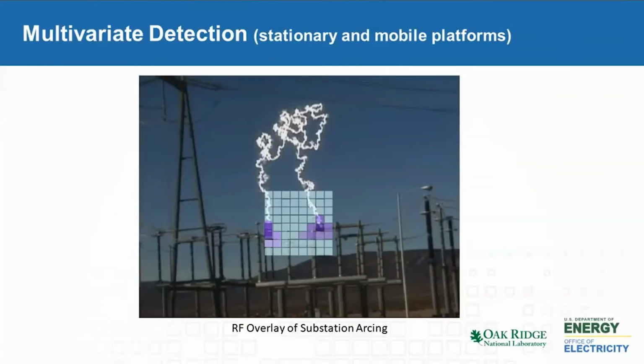So we have good spatial acuity in measurements of what you are measuring at the right radio frequencies at this location, at that location, at the next location. So now we call this augmented reality. It's an overlay of what the RF sensors and the associated software are synthesizing as an image. Here it is, a bunch of squares. The squares change their color based on the intensity. There's some other things based on wavelength. We can do color shifting, and it's overlaid onto an ultraviolet picture of arcing. So that is all wrapped inside the software that's inside that flying little system on top of the drone. Again, you'd say it's AR, an augmented reality where the image is not visible. We're sitting here in the UV, and we've synthesized this RF matrix, RF array, on top of that.